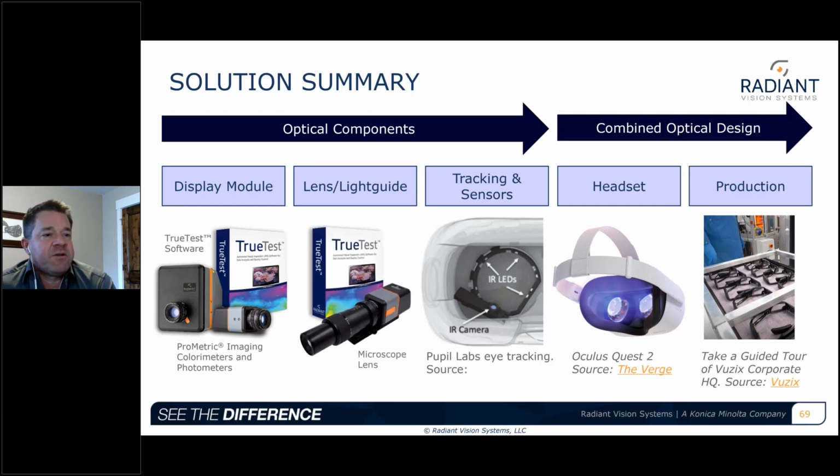As we test optical modules, we can apply the same fundamental imaging systems and software to ensure accurate brightness, color, uniformity, and MTF. Imaging systems can be paired with microscope optics for evaluating extremely small features and fields of view.